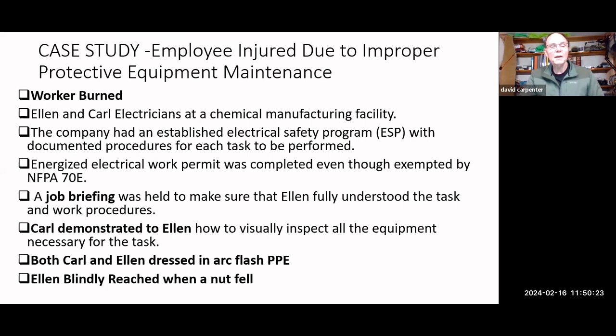Let me see if I can pull this up. The workers were Ellen and Carl. They were electricians at the company. They had an established electrical safety work program and did what they were supposed to do. They got an energized electrical work permit before they started working, and got a job briefing from the supervisor. Carl demonstrated to Ellen, since she was an apprentice and he was the journeyman, how to get around in this equipment. Both Carl and Ellen were dressed in the arc flash protection they should have had.